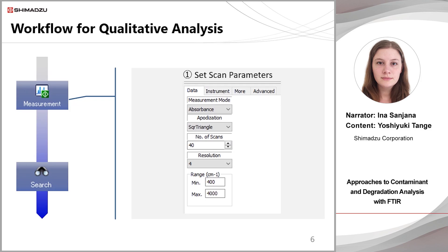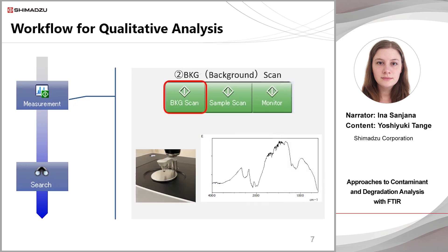Here is an example of the workflow for qualitative analysis with FTIR. First, we need to set the scan parameters, such as the measurement mode and the number of scans. Next, we perform a background scan with nothing on the prism. The energy spectrum, shown on the right, is obtained.